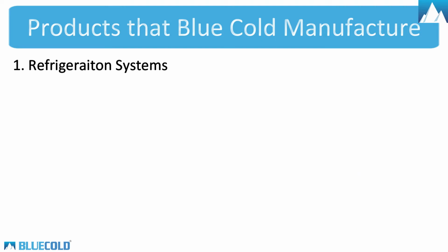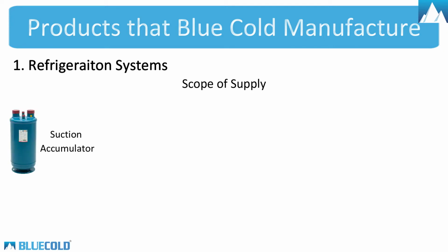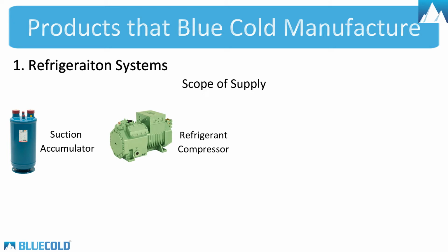Now we are going to see what are the standard scope of supply in our condensing units. Suction accumulator. This is the vessel where the refrigerant is charged at the time of commissioning and connected to the suction line, which is coming from the heat exchanger to recirculate the refrigerant in the system. Refrigerant compressor with ester oil charged. It is the heart of a refrigeration system. It compresses the refrigerant and sends it to the condenser for condensation.